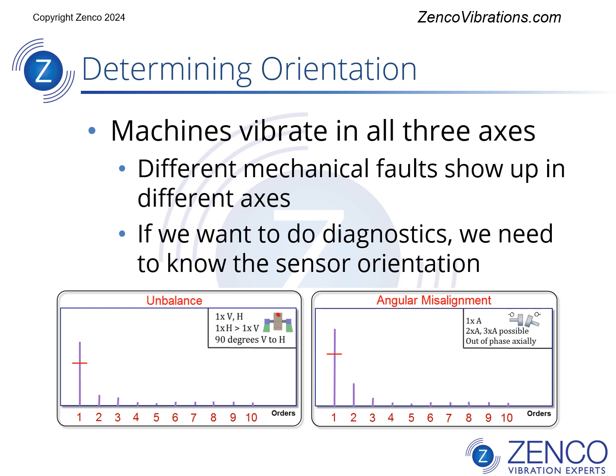Machines vibrate in all three axes. Different mechanical faults show up in different axes. For example, unbalance shows up in the vertical and horizontal directions, whereas angular misalignment shows up in the axial direction. If you want to do diagnostics, you have to know the sensor orientation. It's not enough to just know X, Y, Z, or 1, 2, 3 of your sensor — we need to know how they're oriented compared to the machine.